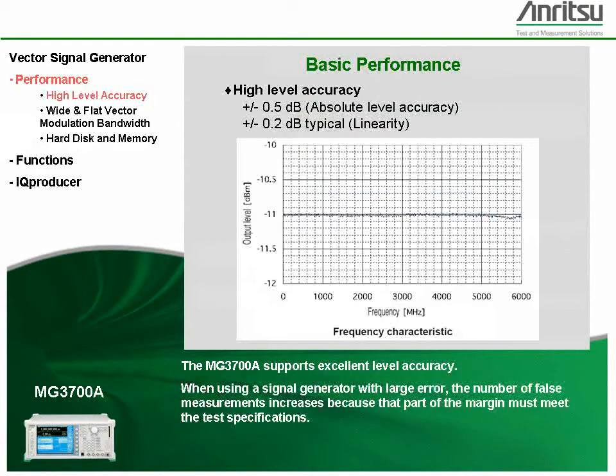The MG3700A supports excellent level accuracy. When using a signal generator with large error, the number of false measurements increases because that part of the margin must meet the test specifications.